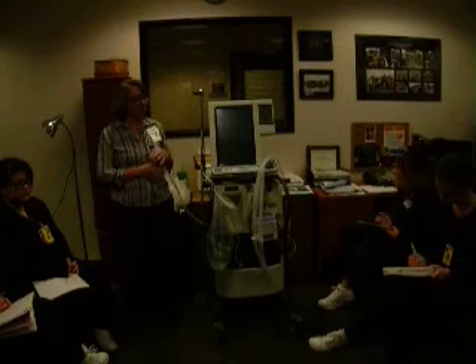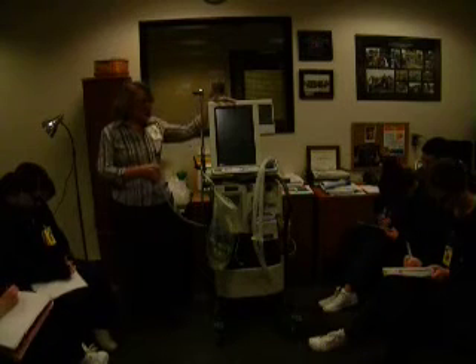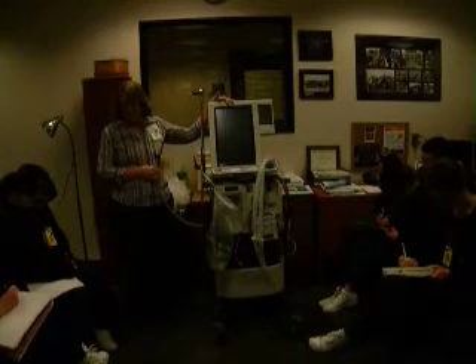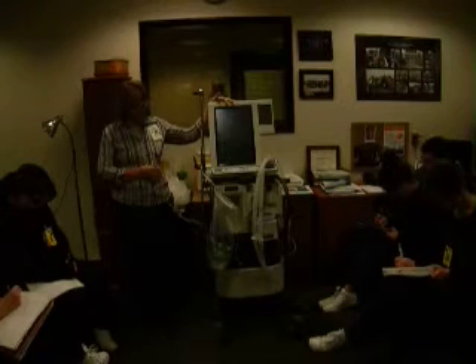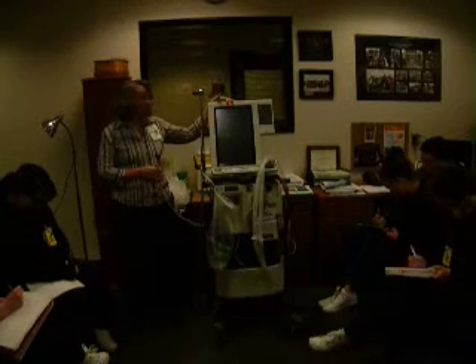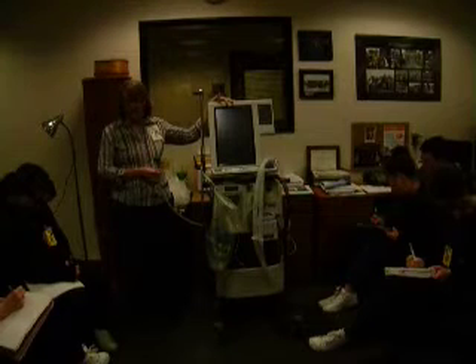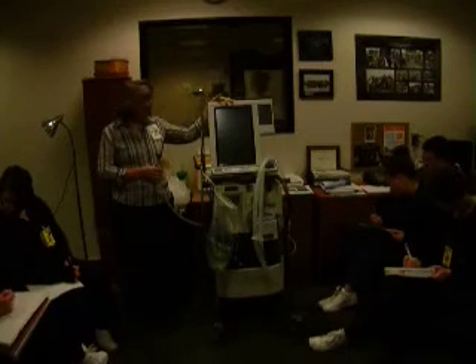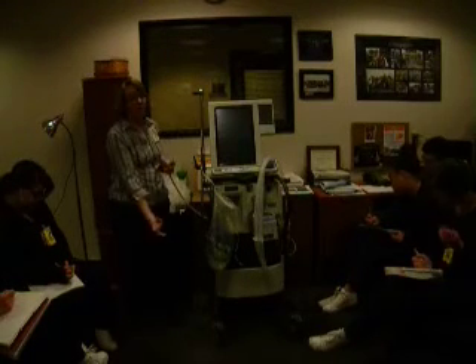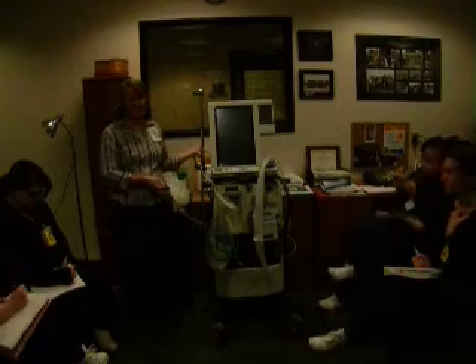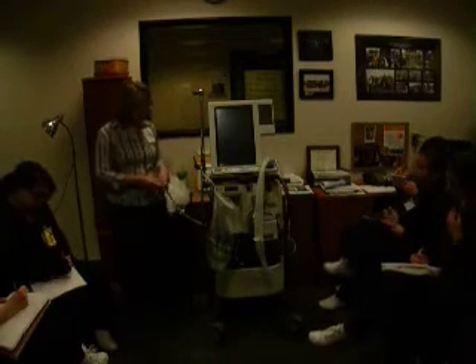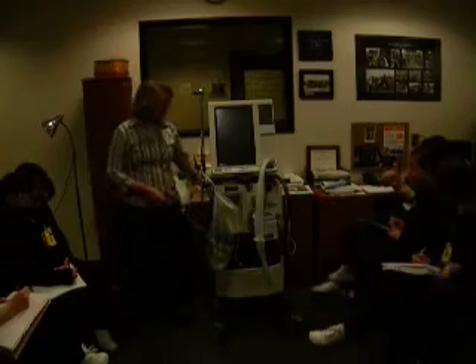So anyways, as we'll talk about more in the coming weeks, the vents have to have some kind of 50 psi power source to run. They require electricity and a 50 psi source. That's hospital vents. That's not every vent. So you have to be plugged into air or oxygen at a minimum, ideally both, and then have your electric source. Because this ventilator has an internal air compressor, I can just run it off electricity because the air compressor will kick in. Now we won't have any oxygen, so we'll have to have it on room air. But we can run it without having to plug it into the wall.